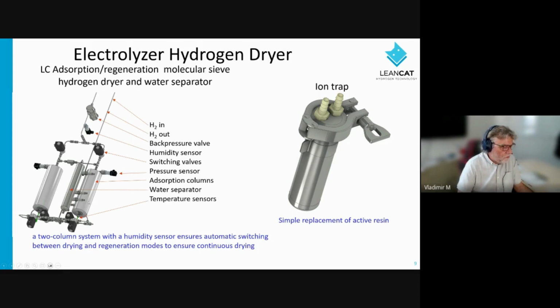The system is composed of two columns of adsorption using molecular sieves, and the system can work continuously because one column is working. It means it's absorbing humidity from hydrogen, and the other is regenerated. Because when the system starts to be saturated, we can measure that with a humidity sensor, and the system switches automatically, and we start to use this one, and the other column starts to be heated for the regeneration.